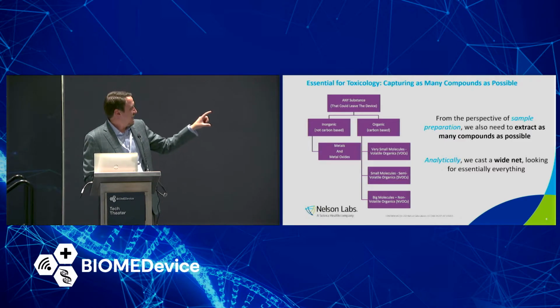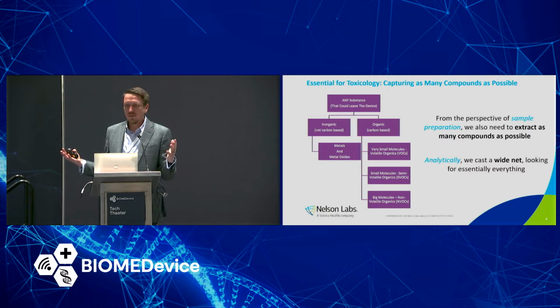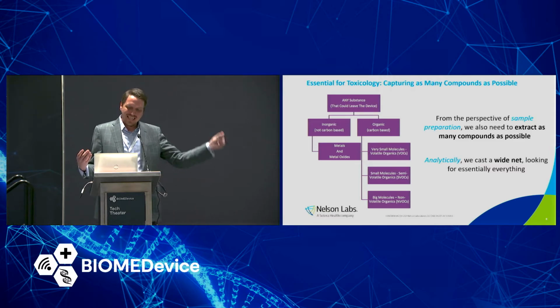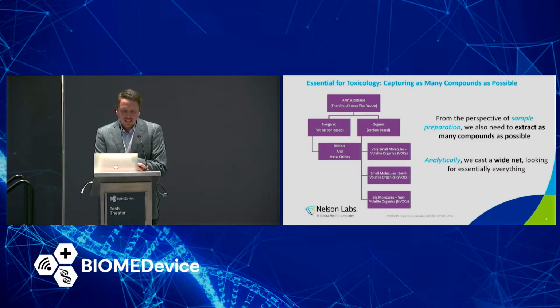As I said, we need to extract as many compounds as possible because it's difficult to predict what might come out. Analytically, we cast a really, really wide net looking for everything that could come off of the device. From a chemistry perspective, that's a really challenging problem. So we're not looking for just a list of plasticizers or a short list of metals. We need an open scan type methodology. And this is something that the FDA has been very clear on, and they continue to sort of refine and expand what they mean by an open scan.